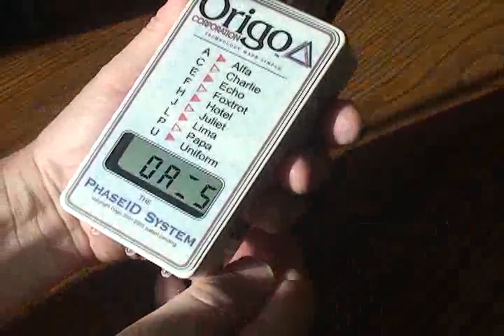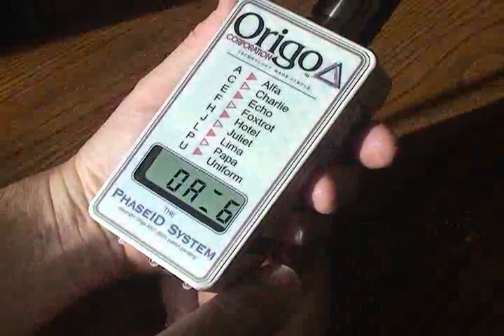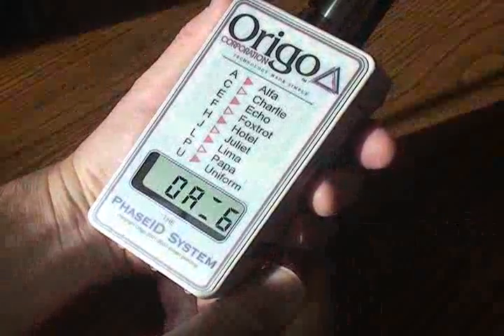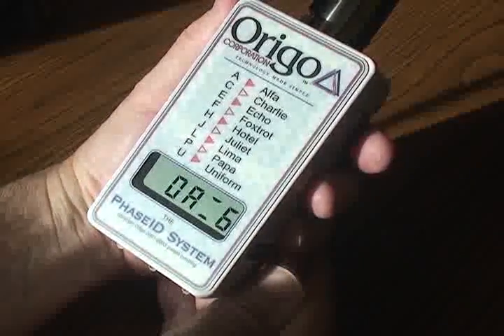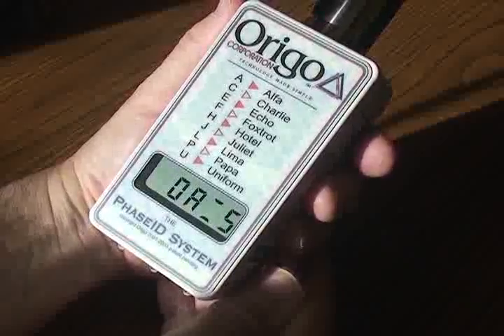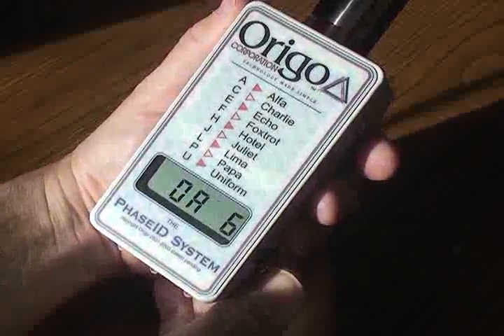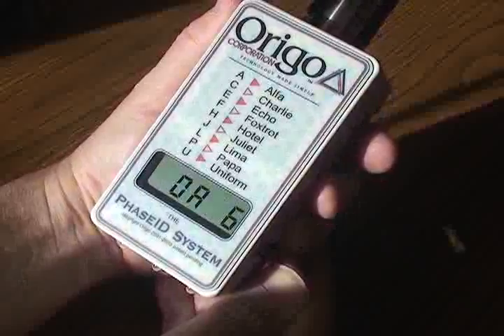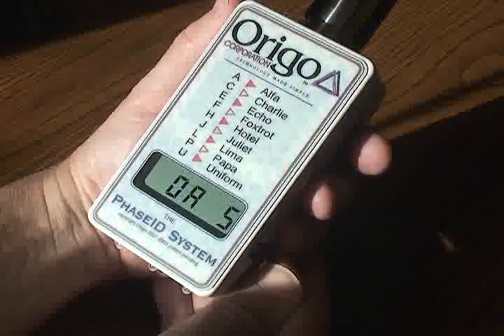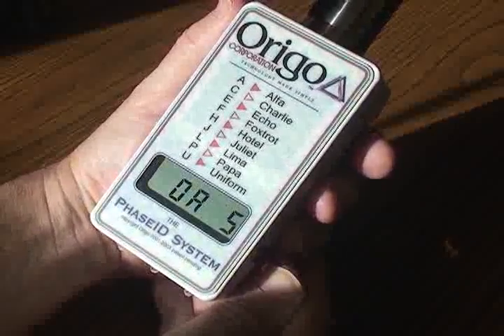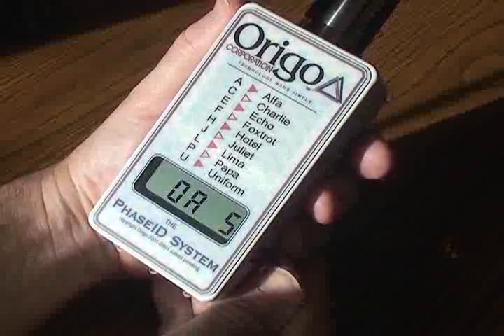You always have to touch the button to turn it off after you take a reading, because it won't disconnect from the voltage if you don't. The sensitivity is such there's always some stray voltage, so you have to turn it back off into the OA position.